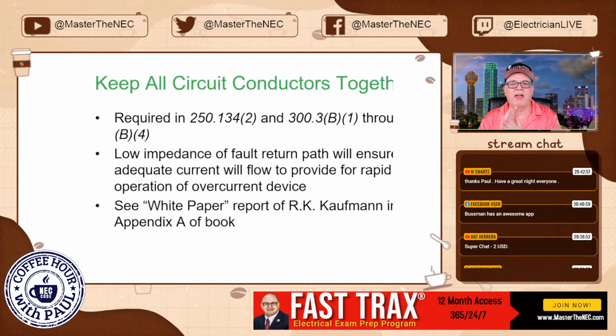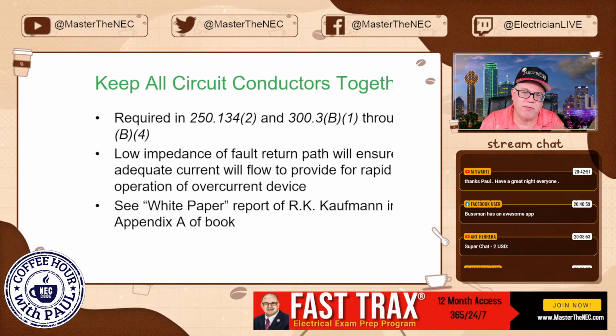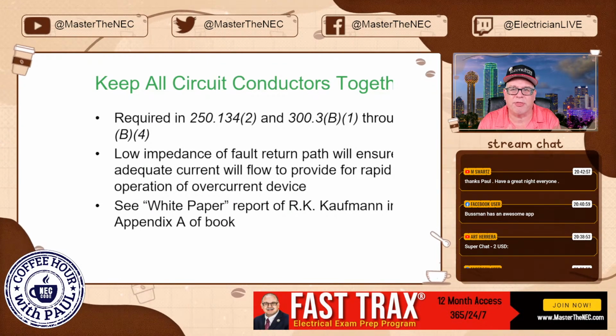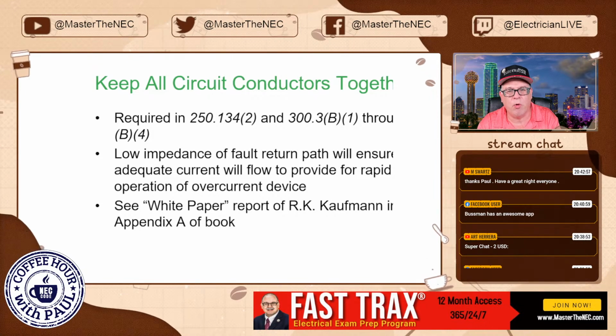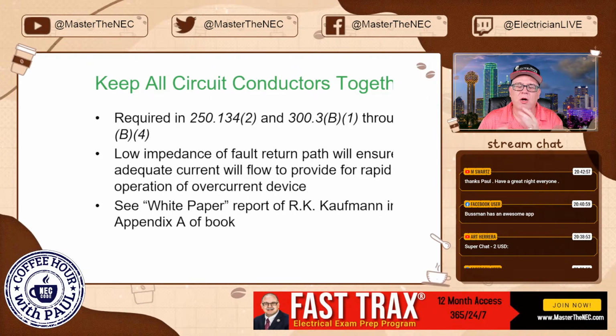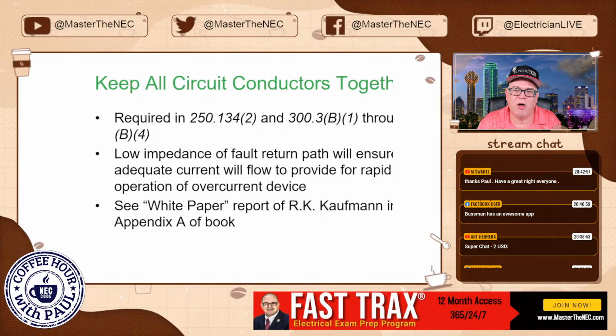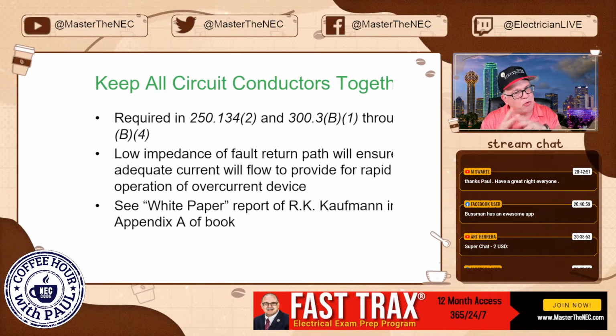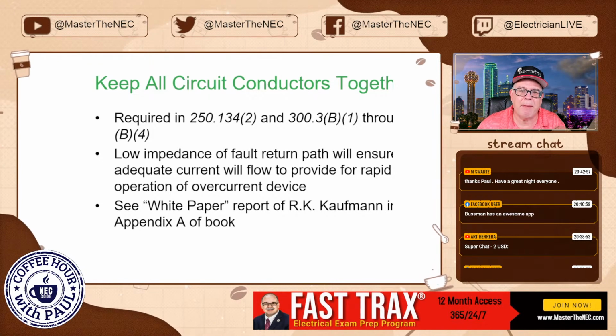Keep all circuits together. Again, required by 250.134.2 and 300.3B1 through B4. Talk about this. Low impedance of the fault return path will ensure adequate current will flow, keeping those circuits running together, and rapid operation of the device.